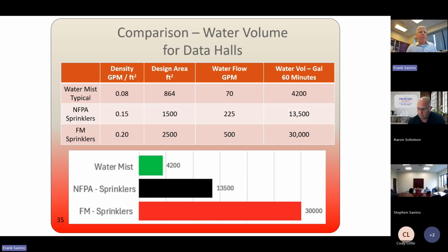And again, Factory Mutual would have no problem with water mist. If you said, hey, we're going to put water mist in accordance with FM standards in this data center, they say, great, just follow our guidelines. And AHJs feel the same way. We've done many, many water mist systems. They consider water mist systems to be an approved, acceptable fire suppression system that's gone through all the testing to prove its efficacy and effectiveness. Any questions on that?